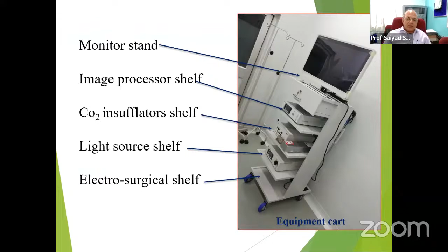in your machine. In the insufflating system, you have the design to deliver the gas, only deliver the gas, from the machine to the abdominal cavity or any other cavity where you want to do the surgery. Insufflation pressure can be set from 0 to 30 mmHg. This is the range of the setting. Gas flow volume can be set from 0 to 9.9 liters per minute.